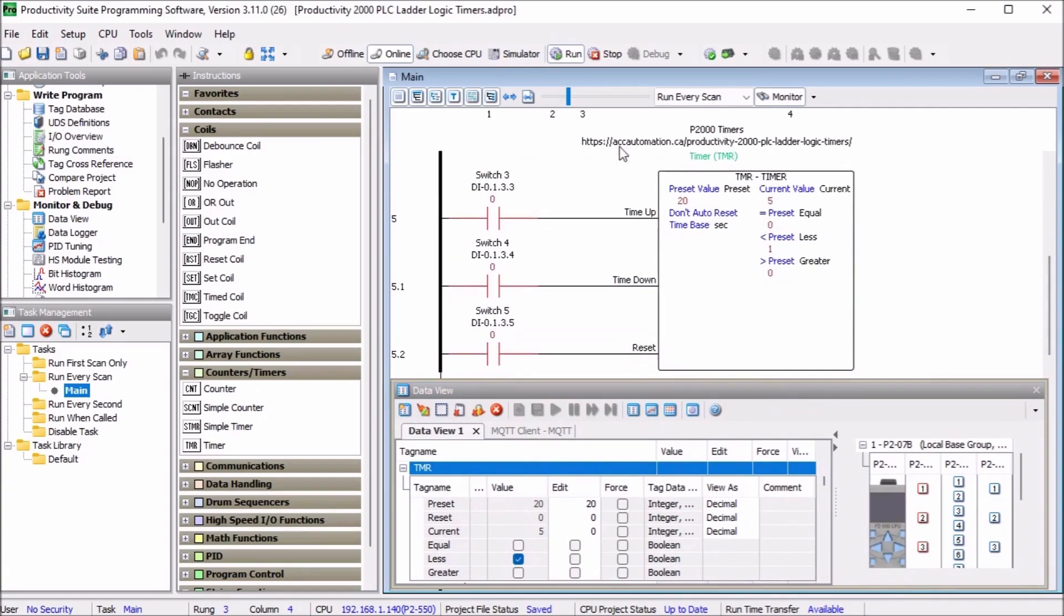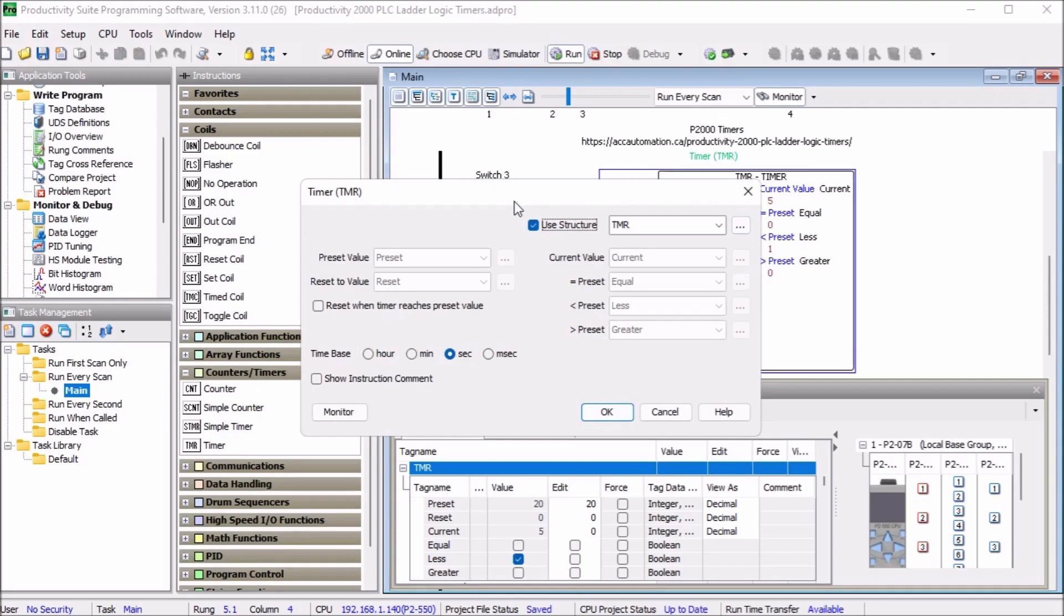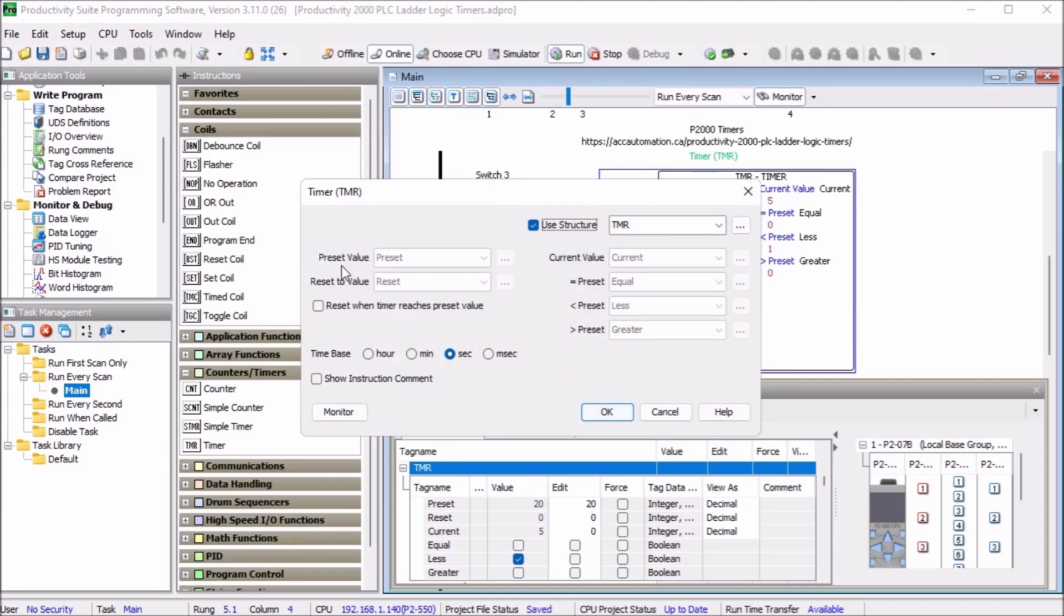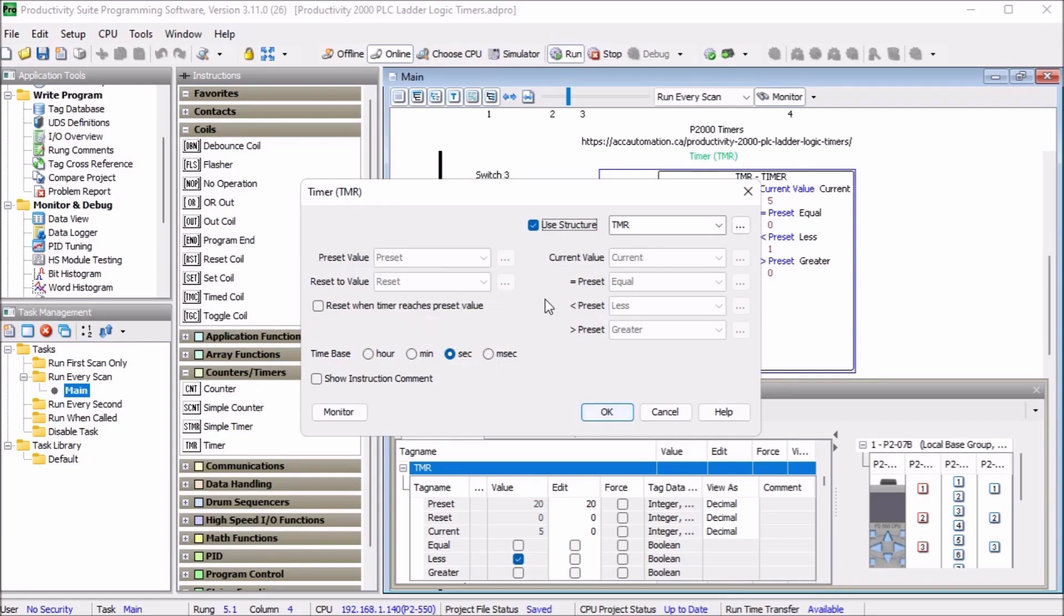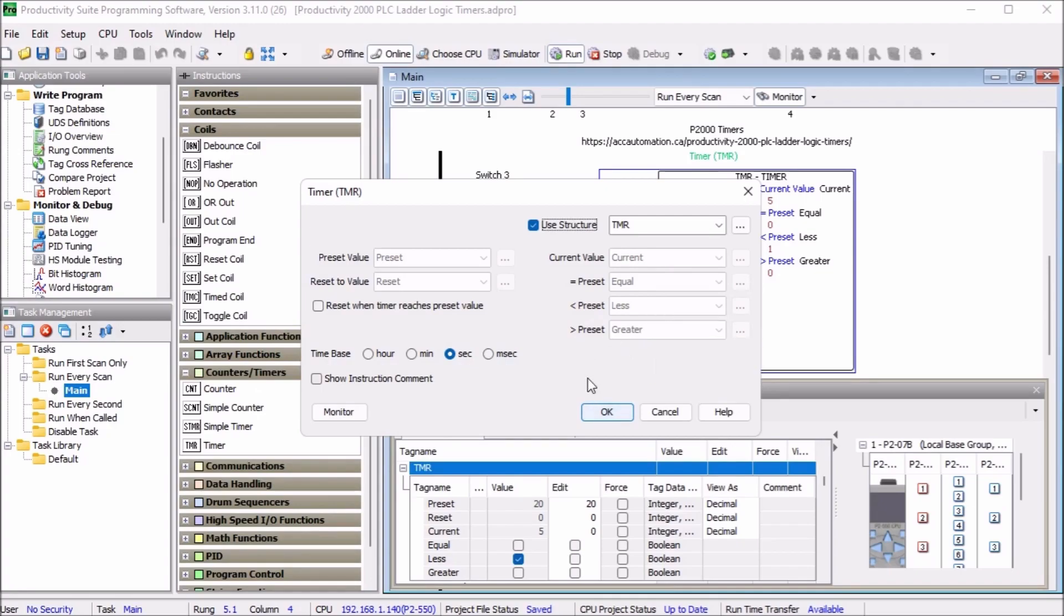We'll close this off delay, open up the timer and we will move that down a little bit as well as look at our actual timer instruction. So we actually have three inputs to this timer. We have switch number three, which times up, switch number four times down, and we have switch number five resets, which brings the reset value back into that counter. Now on the output side, we have three bits as well. We have an equal, less or greater bit that will actually trigger the output for us. So let's take a look at the instruction itself. And you can see that we are using a structure TMR. And that gives us our preset value, which we will set for 20 seconds, time base rate right here. And then we'll reset to value is our reset value. In this case here, we'll use zero. Our current value, which is the current value in the timer right now, are equal to less than and greater than bits that will be triggered based on this timer. So that is the structure of our timer itself.